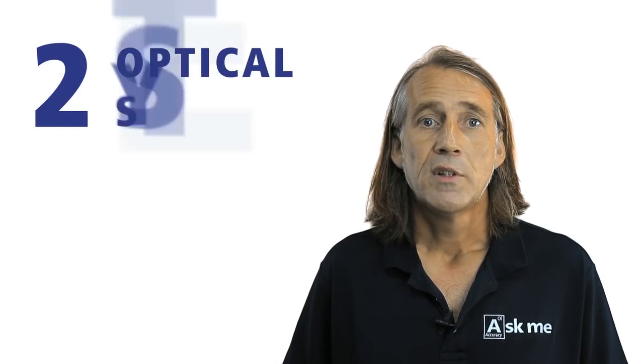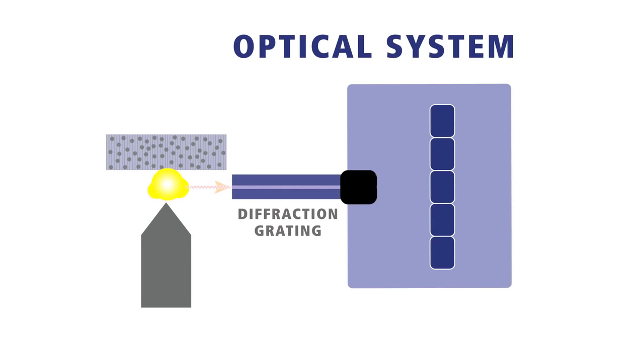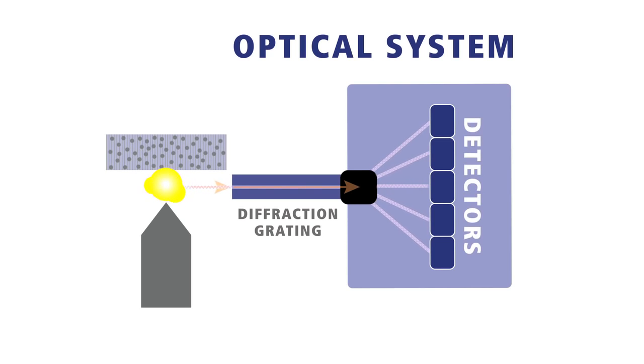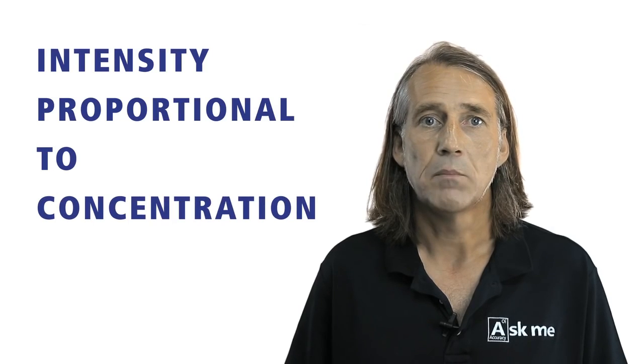The second component is an optical system. The light — the multiple optical emission lines from the vaporized sample, known as the plasma — passes into the spectrometer. A diffraction grating in the spectrometer separates the incoming light into element-specific wavelengths, and a corresponding detector measures the intensity of light for each wavelength. The intensity measured is proportional to the concentration of each element in the sample.